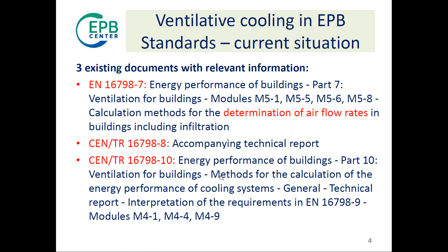In EN 16798-7, the relevant content includes methods for the calculation of airflow rates, for instance entering and leaving through open windows, also applicable not only to windows but to leakages, vents, any opening that can be used to apply natural ventilation to a building or zone.